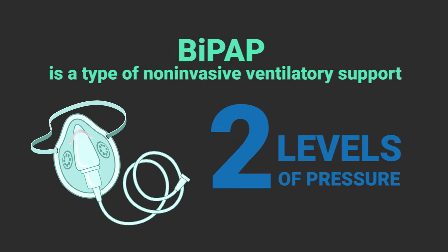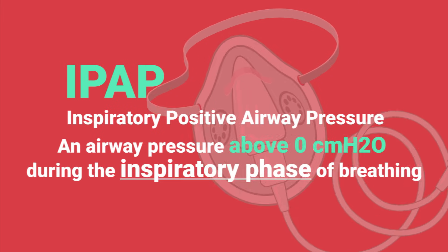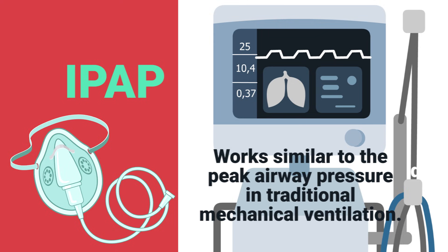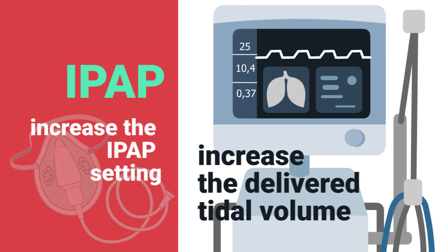IPAP stands for inspiratory positive airway pressure. It's an airway pressure that is above zero during the inspiratory phase of breathing. It works similar to the peak airway pressure in traditional mechanical ventilation, so if you were to increase the IPAP setting, this will increase the delivered tidal volume.